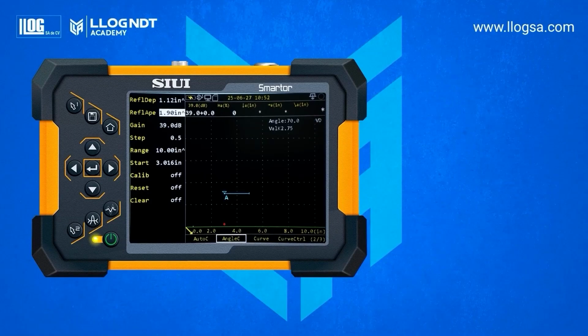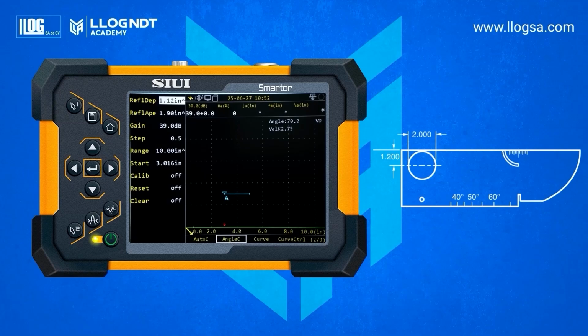Refraction angle verification. We will access the Angle Calibration submenu and verify the ultrasound beam path angle. 2 reference values must be entered. The first is the depth of the hole, which we will use for verification. The depth is 1.2 inches. This is the value we must enter as reference 1. The second reference corresponds to the diameter or aperture of the hole. In this case, 2 inches.